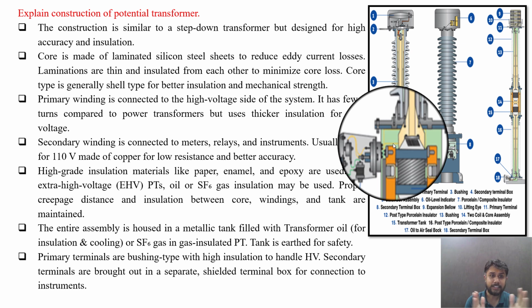The entire assembly is housed in a metallic tank filled with transformer oil for insulation and cooling purposes, or SF6 gas in gas insulated potential transformer. The tank is earthed for safety purposes.